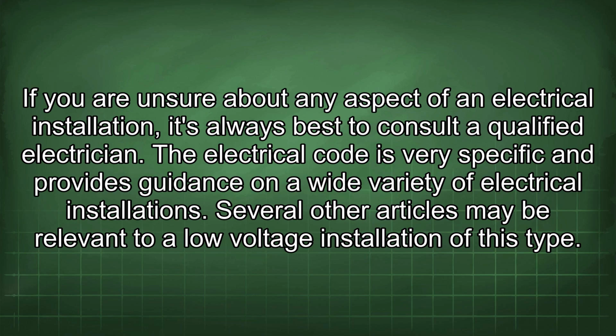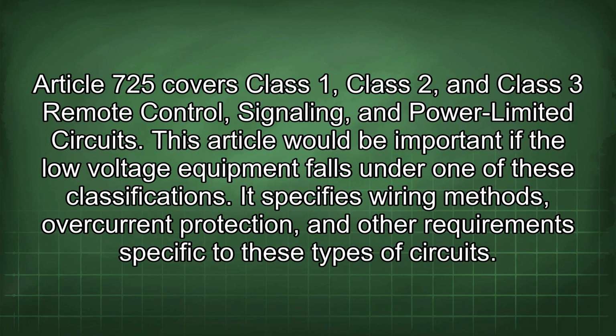Several other articles may be relevant to a low-voltage installation of this type. Article 725 covers Class 1, Class 2, and Class 3 remote control, signaling, and power-limited circuits. This article will be important if the low-voltage equipment falls under one of these classifications. It specifies wiring methods, overcurrent protection, and other requirements specific to these types of circuits.